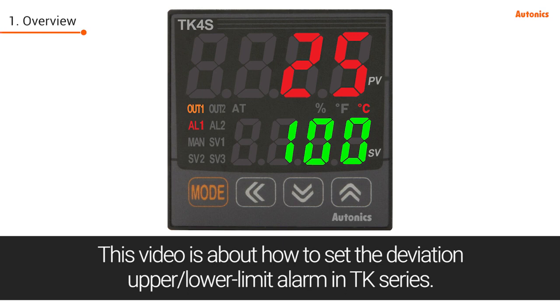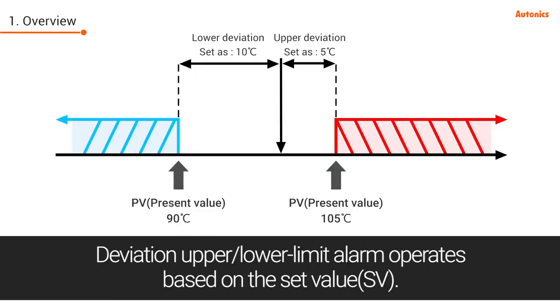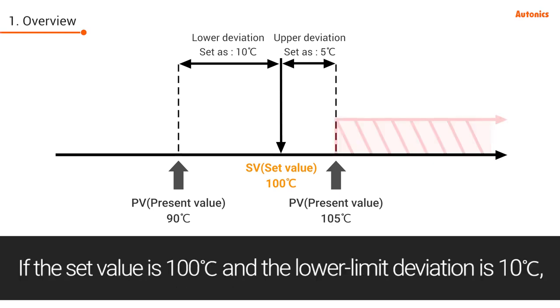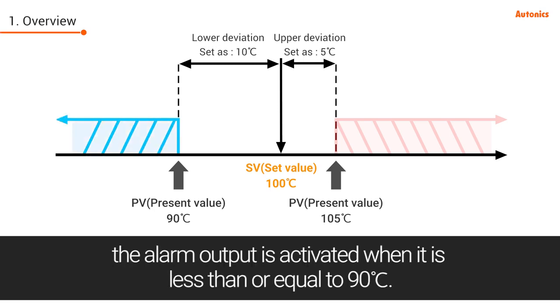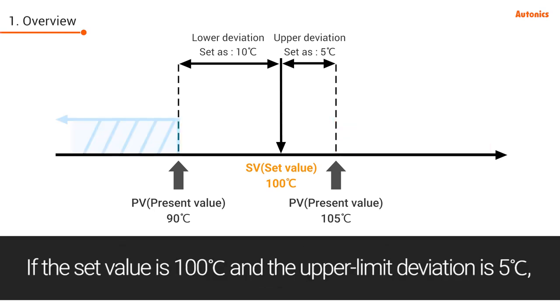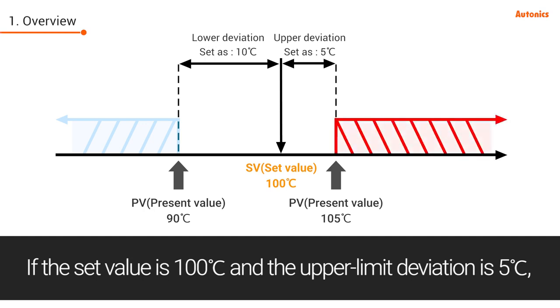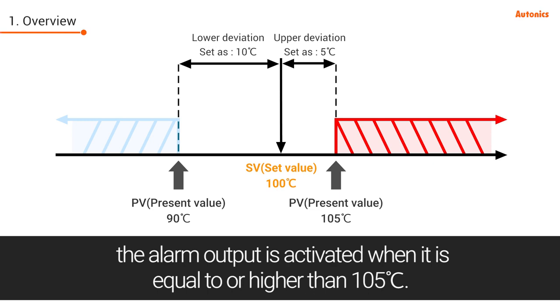This video is about how to set the deviation upper lower limit alarm in the TK series. The deviation upper lower limit alarm operates based on the set value. If the set value is 100 degrees and the lower limit deviation is 10 degrees, the alarm output is activated when it is less than or equal to 90 degrees. If the set value is 100 degrees and the upper limit deviation is 5 degrees, the alarm output is activated when it is equal to or higher than 105 degrees.